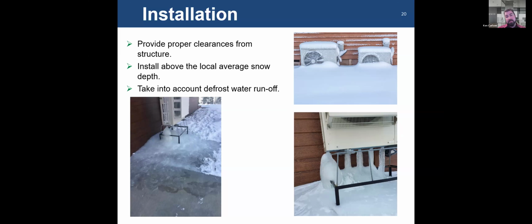You can actually drain these to a different position. They do make little fittings. You can put in a drain line. If you did something like that, you would need to put heat trace on that drain line to make sure that water will actually drain out and to another location. Avoid placing these units near walkways. Shown in the picture on the left, and I can't tell you if that's a walkway or patio or whatever it might be, but that defrost water that's been melted is piling up, and now it's making its way over to a walkway. You're going to end up with a slipping hazard. Don't mount this over a walkway in a cold climate.